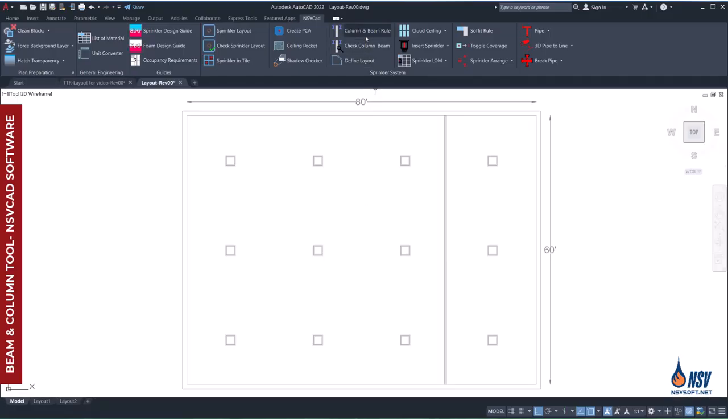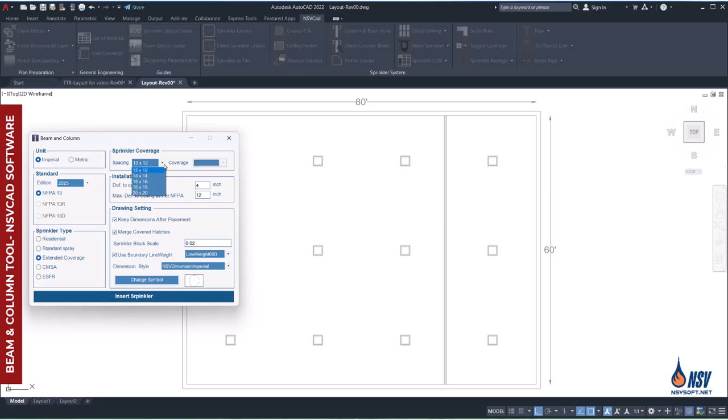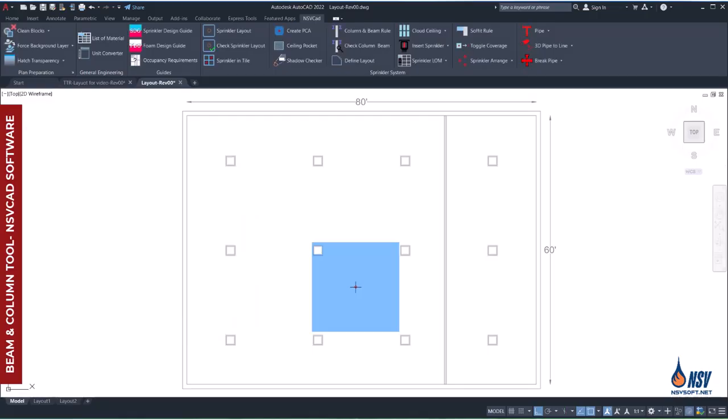After launching the app, we begin by entering key information, including the edition of the standard, the sprinkler type, and the coverage area. For this example, we'll assume the distance between the deflector and the ceiling is 6 inches. Based on the selected sprinkler type, Extended Coverage, the software automatically applies the 4x rule.